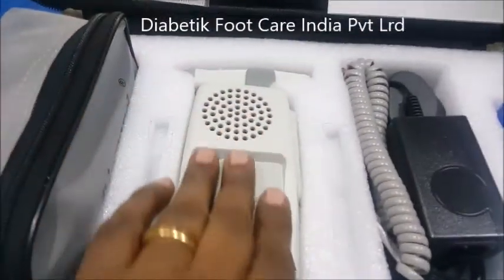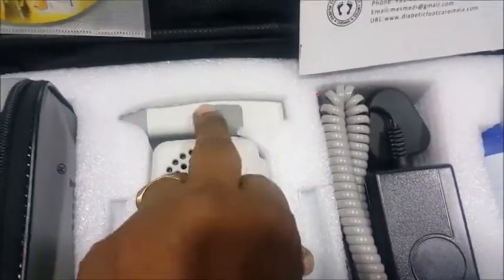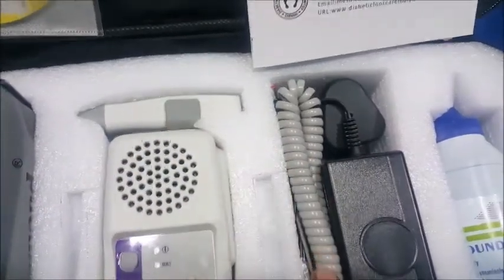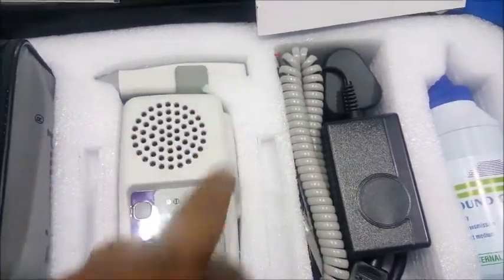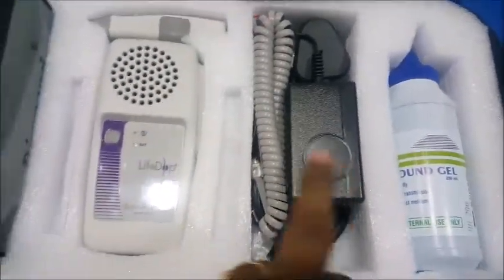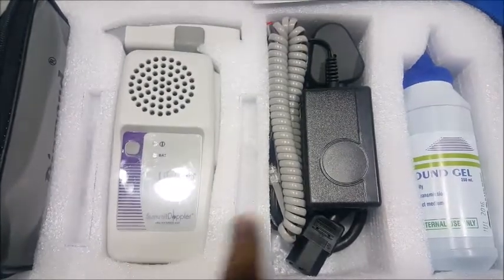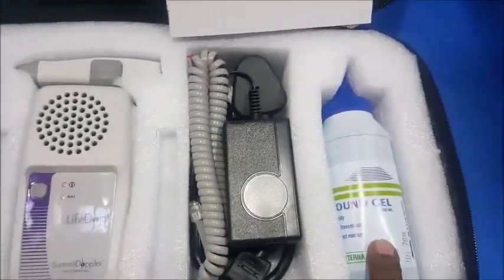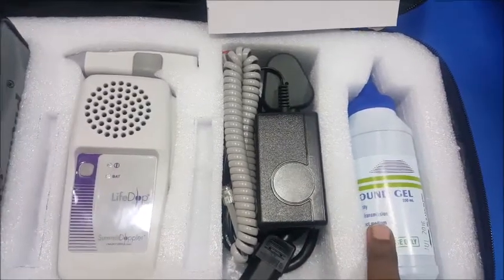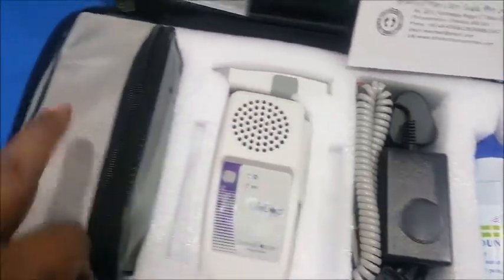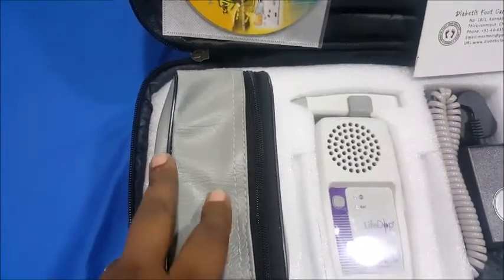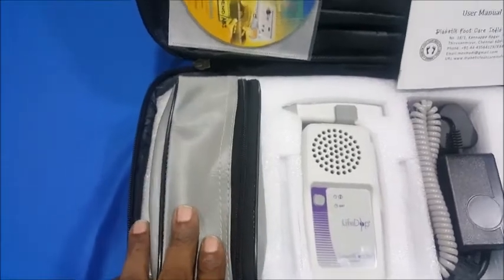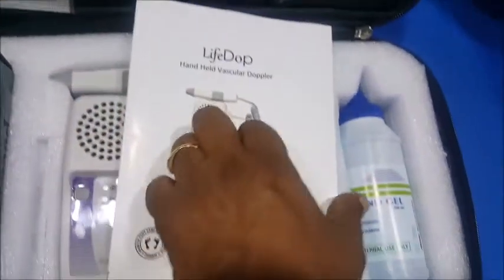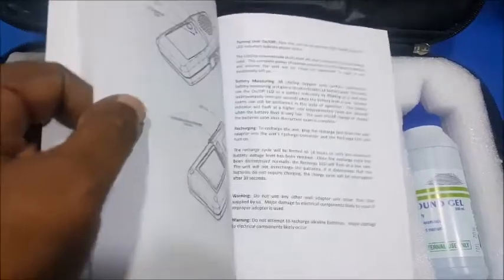So you will have the Doppler. This is a Doppler L150R, and you have the 8 MHz transducer here, and this white gray color cable connects the transducer to the unit, and this is a charger. This unit works on rechargeable battery, and this is a charger for it. And we also supply an ultrasound gel, about 250 grams, and then we have a sphygmomanometer, dial type, for measuring the ankle brachial index. We have a detailed instruction manual. This tells about the procedures, how to measure the ABI and other details.